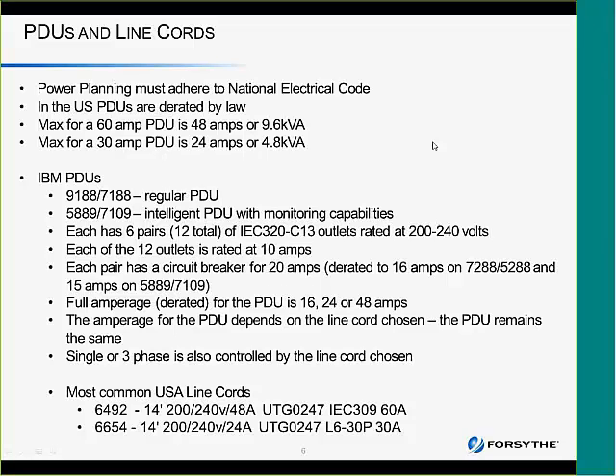But each of the pairs has a circuit breaker for 20 amps, which of course gets derated to 16 amps on the 7188, and 15 amps on the 5889, 7109 pair. Therefore, you can't basically commit to more than around 16 amps on a pair. Very bizarre. So the full amperage for the PDU is either going to be 16, 24, or 48 amps, depending on what you actually have for a line cord.